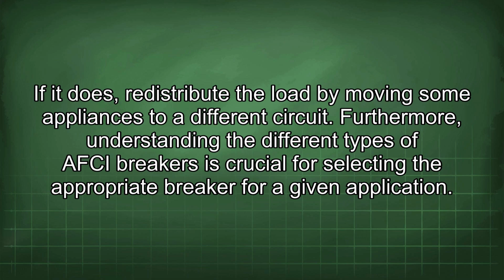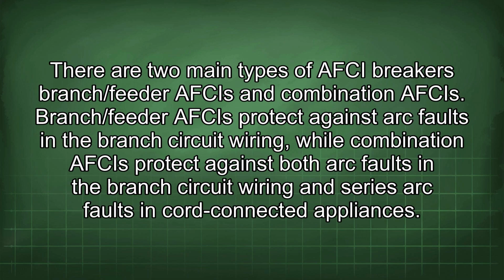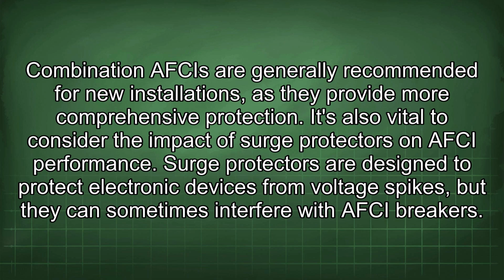Furthermore, understanding the different types of AFCI breakers is crucial for selecting the appropriate breaker for a given application. There are two main types of AFCI breakers: branch/feeder AFCIs and combination AFCIs. Branch/feeder AFCIs protect against arc faults in the branch circuit wiring, while combination AFCIs protect against both arc faults in the branch circuit wiring and series arc faults in cord-connected appliances. Combination AFCIs are generally recommended for new installations, as they provide more comprehensive protection.